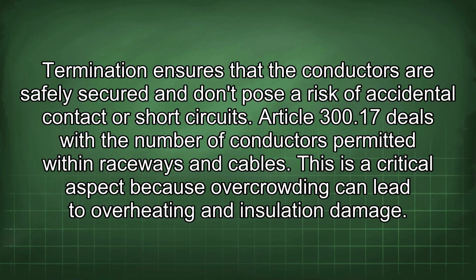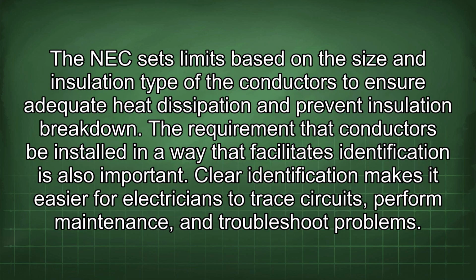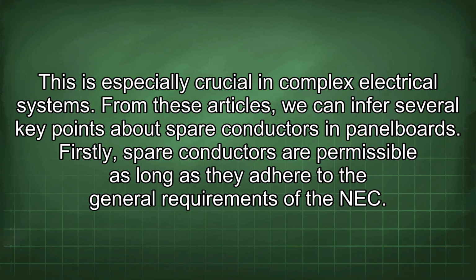Article 300.17 deals with the number of conductors permitted within raceways and cables. This is a critical aspect because overcrowding can lead to overheating and insulation damage. The NEC sets limits based on the size and insulation type of the conductors to ensure adequate heat dissipation and prevent insulation breakdown. The requirement that conductors be installed in a way that facilitates identification is also important. Clear identification makes it easier for electricians to trace circuits, perform maintenance, and troubleshoot problems. This is especially crucial in complex electrical systems.